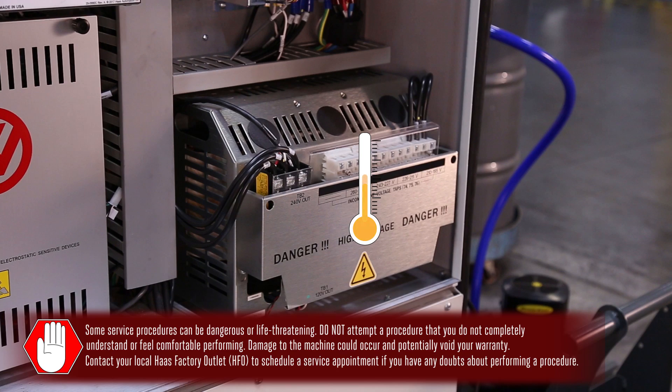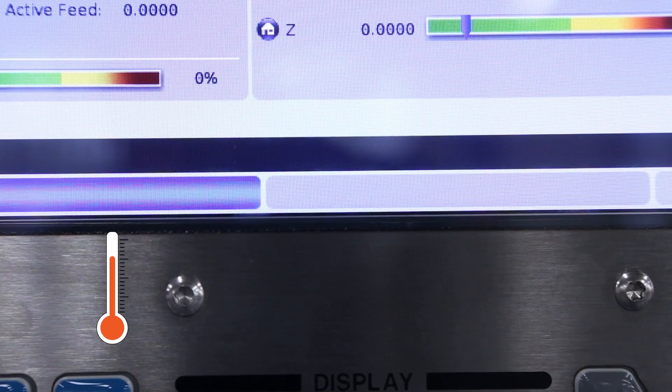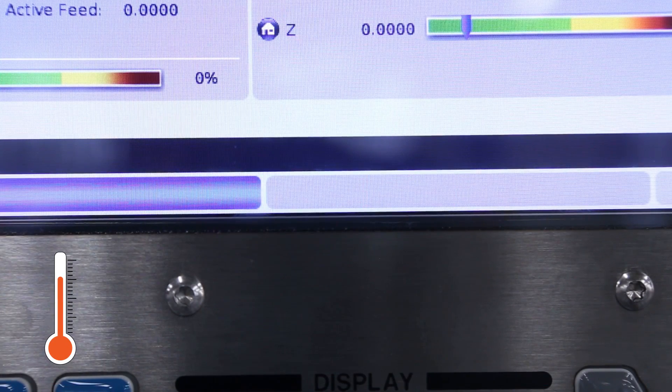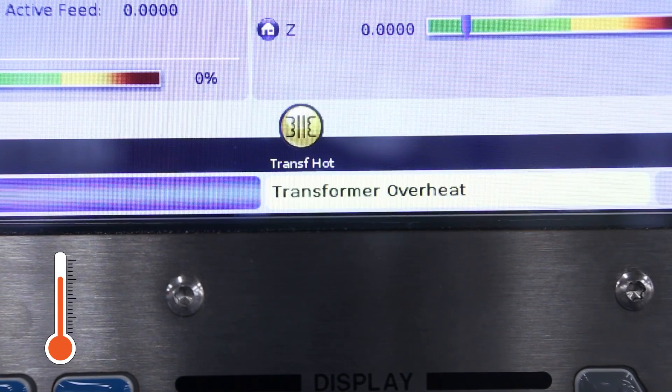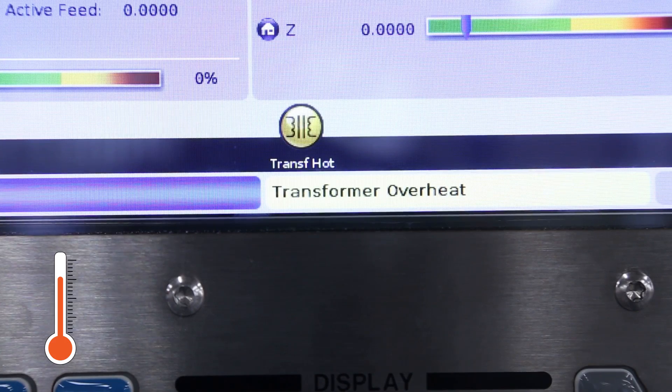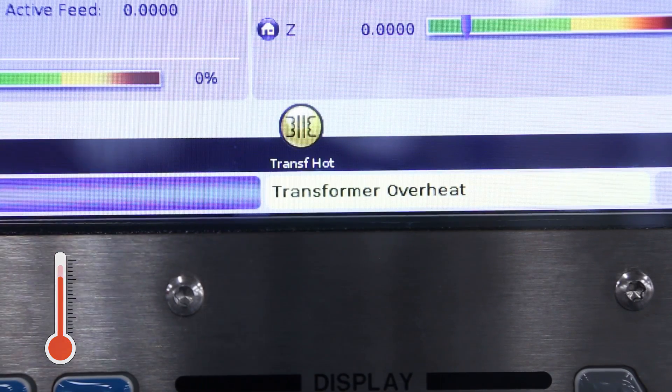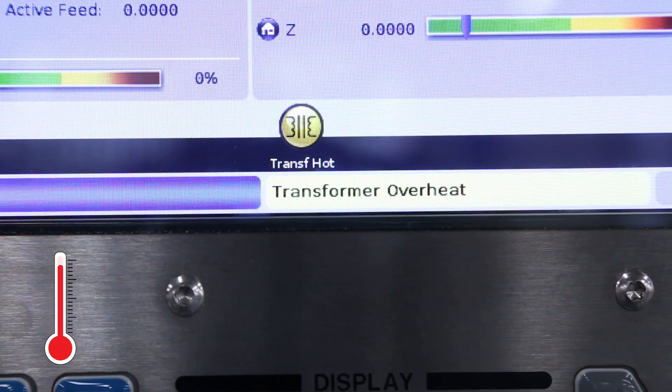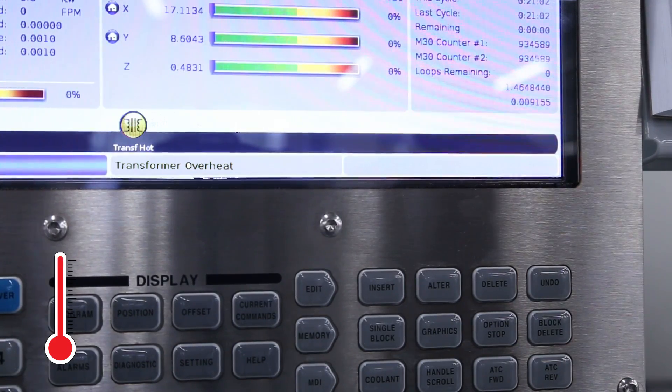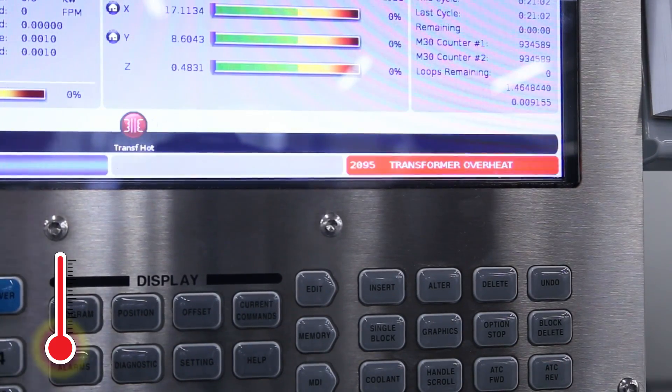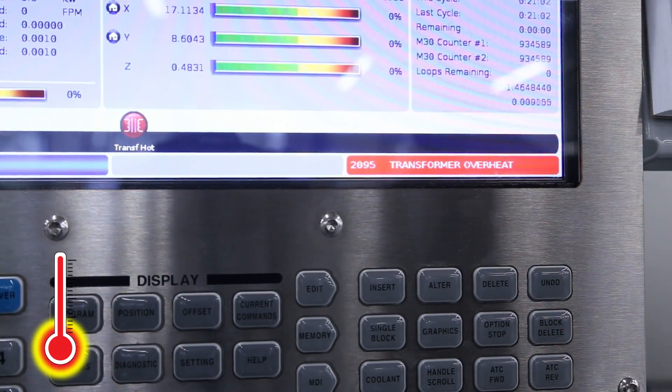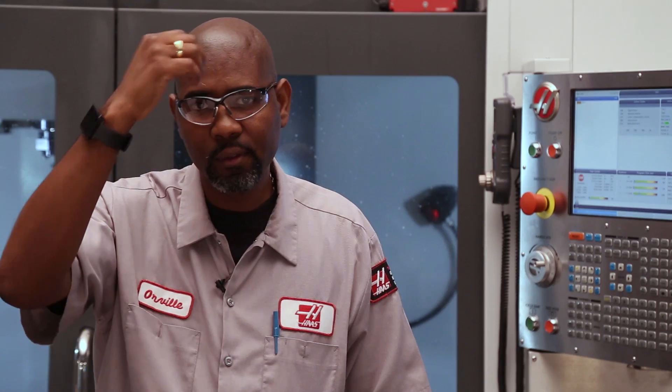When the transformer temperature reaches a preset value, the control generates a warning icon on the display. If the temperature continues to rise, the control triggers alarm 2095 transformer overheat.